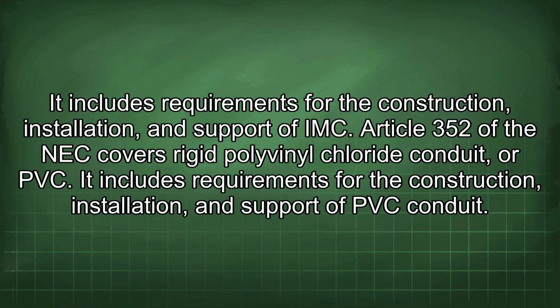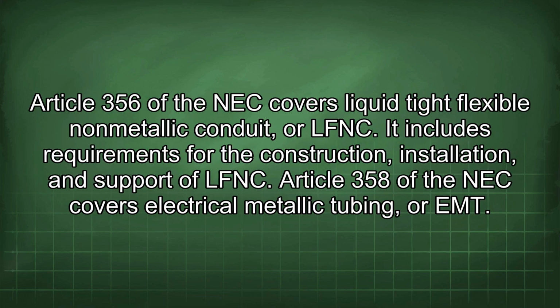Article 352 of the NEC covers rigid polyvinyl chloride conduit, or PVC. It includes requirements for the construction, installation, and support of PVC conduit. Article 356 of the NEC covers liquid tight flexible nonmetallic conduit, or LFNC. It includes requirements for the construction, installation, and support of LFNC.